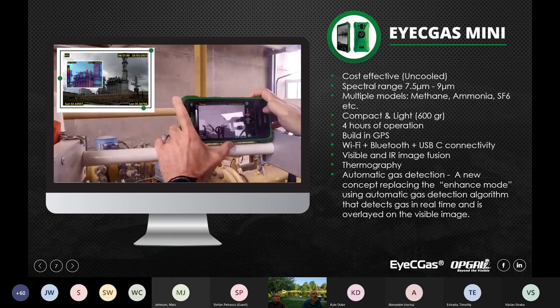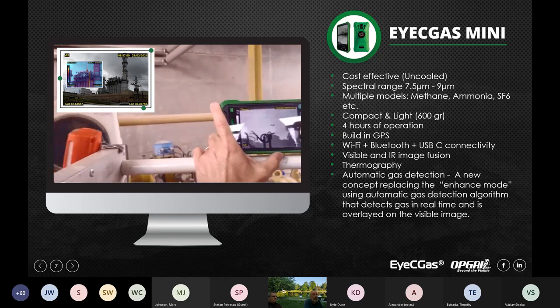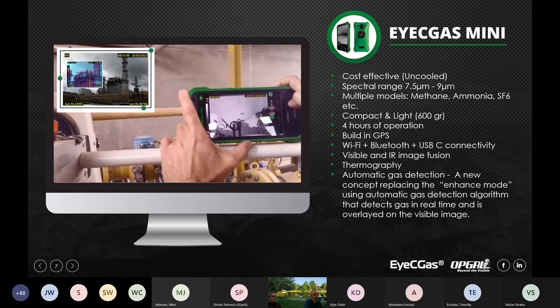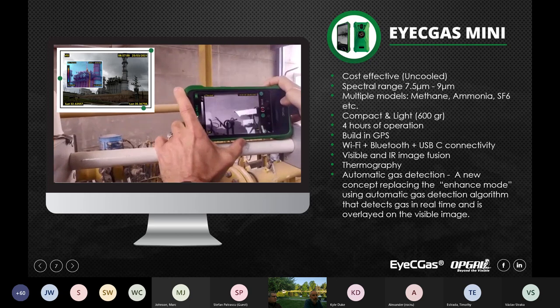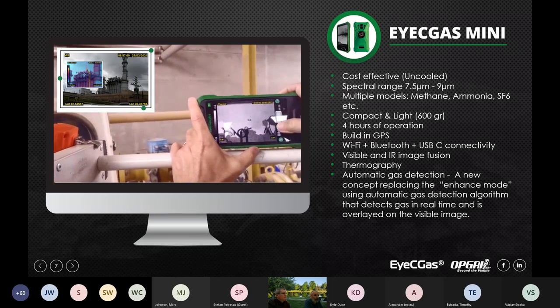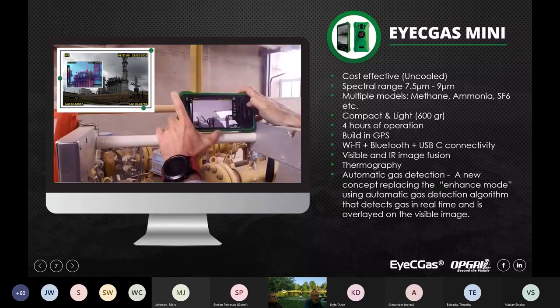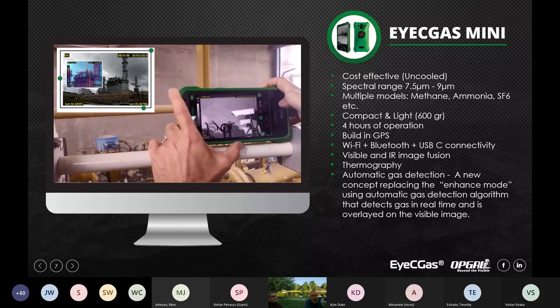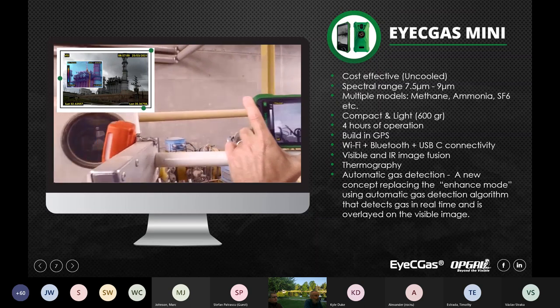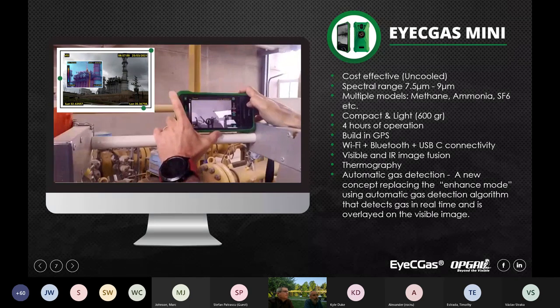The EyeCGas Mini is our uncooled product. Being uncooled makes it a lot more cost-effective, but it has its limitations as well — this is a methane-only camera, though we also have two versions for ammonia and SF6. It's compact and very light. We replaced the enhanced mode from the EyeCGas 2.0 with an automatic gas detection mode, which colorizes the screen on top of the visible image. This helps compensate for the fact that it's not as sensitive compared to the EyeCGas 2.0.